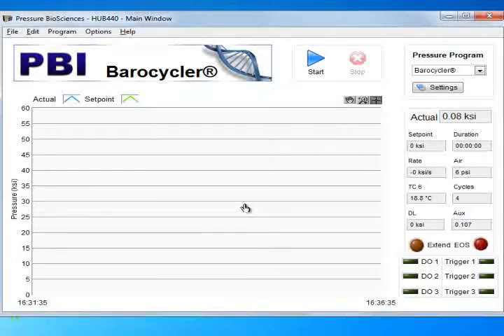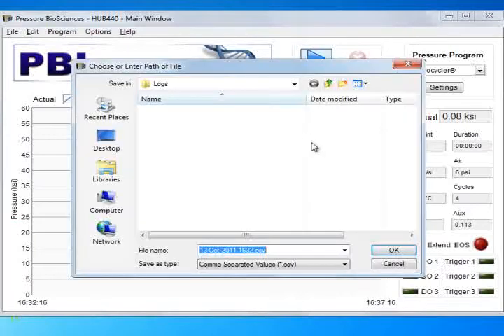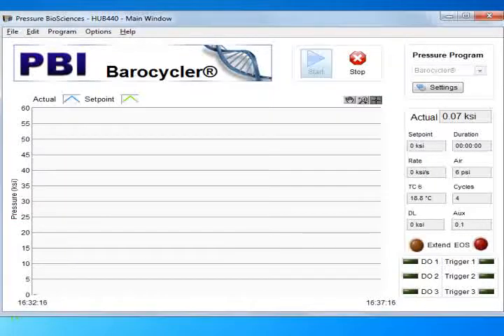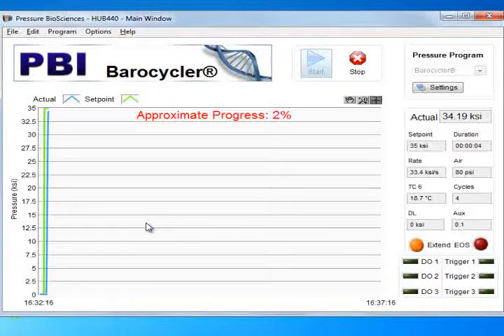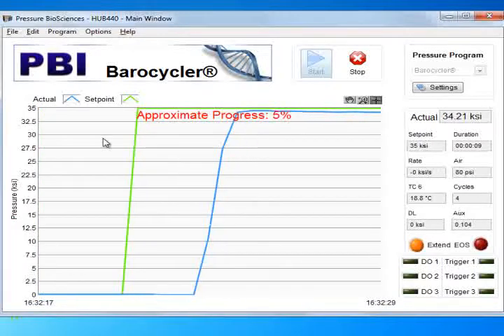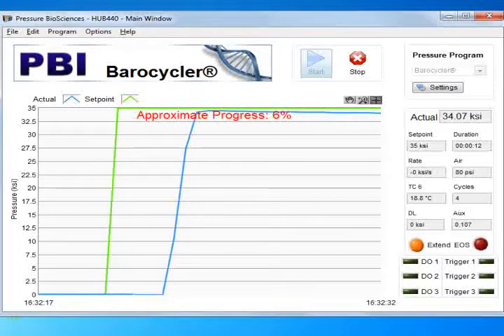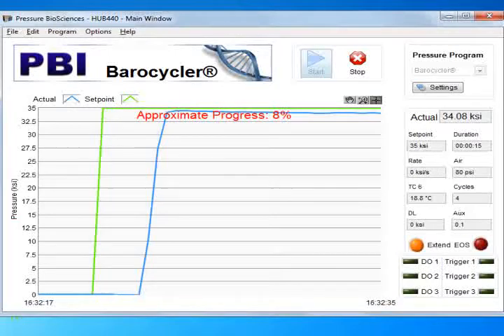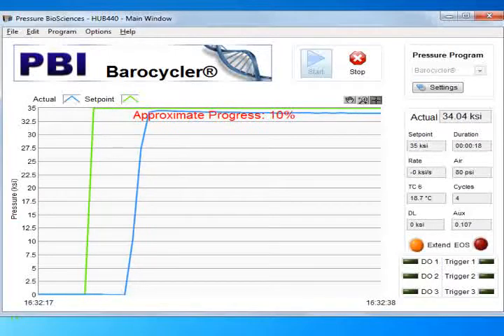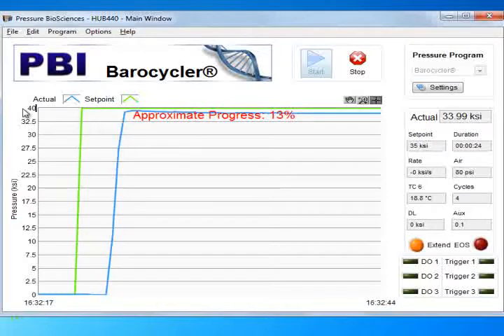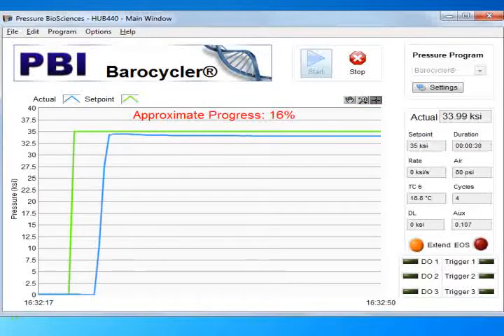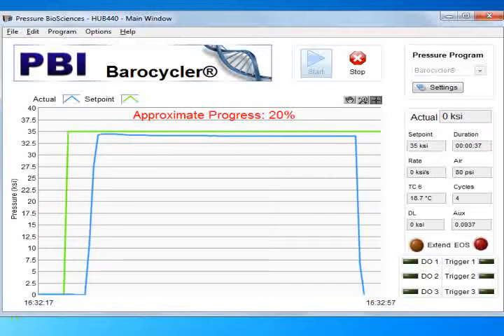The software prompts the user for the location and the name of the data log file, which by default is automatically named by the software using a combination of date and timestamps. At this point, the expected and the actual pressure are presented on the graph in real time. Please note that the user can tell the software to automatically scale the data on either axis of the graph. Alternatively, one can disable the auto scale feature and scale the graph manually by typing the maximum value directly at the graph axis. The first cycle is almost over.